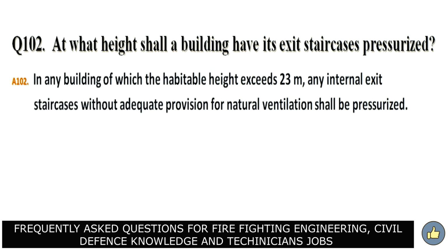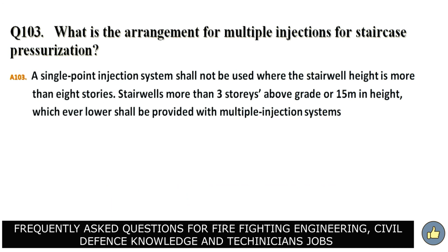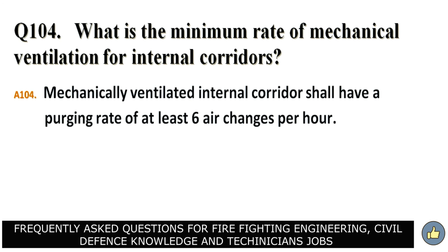At what height shall a building have its exit staircases pressurized? Answer. In any building of which the habitable height exceeds 23 meters, any internal exit staircases without adequate provision for natural ventilation shall be pressurized. What is the arrangement for multiple injections for staircase pressurization? Answer. A single point injection shall not be used where the stairwell height is more than 8 stories. Stairwells more than 3 stories above grade or 15 m in height, whichever is lower, shall be provided with multiple injection systems. Question number 104.